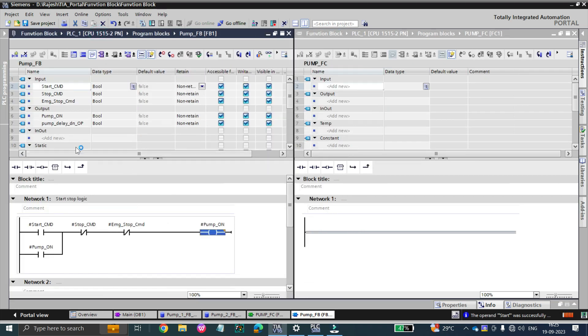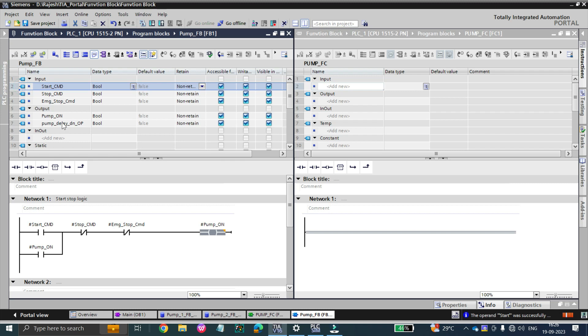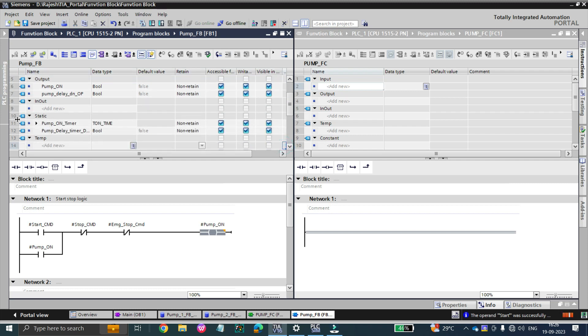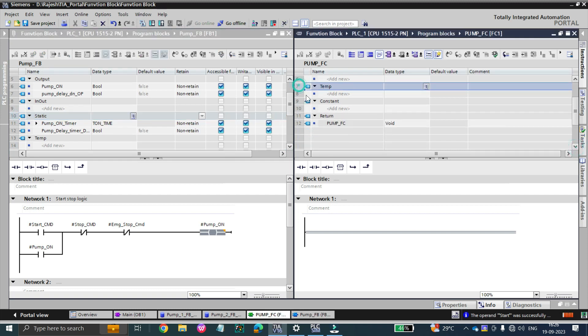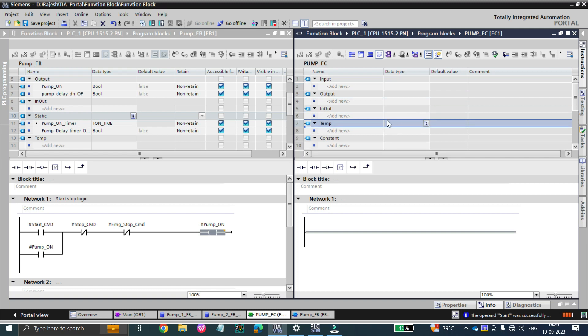We'll discuss the difference between local values in function block and in function. Both function block and function have input tags — these are called local tags. This is the function's local view and this is the function block's local view. Both have inputs and outputs. However, you can see that function block has 'static' but in function you can't find a static value.